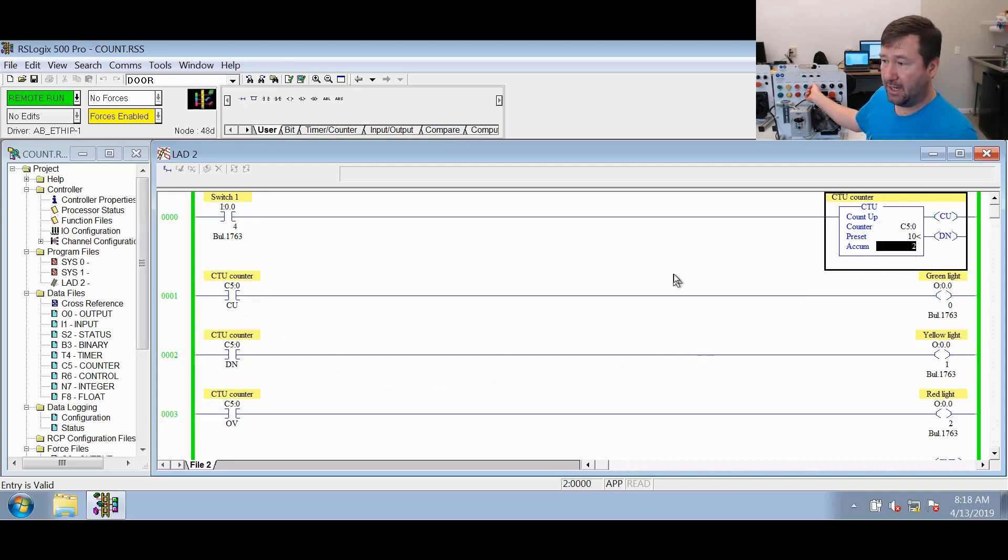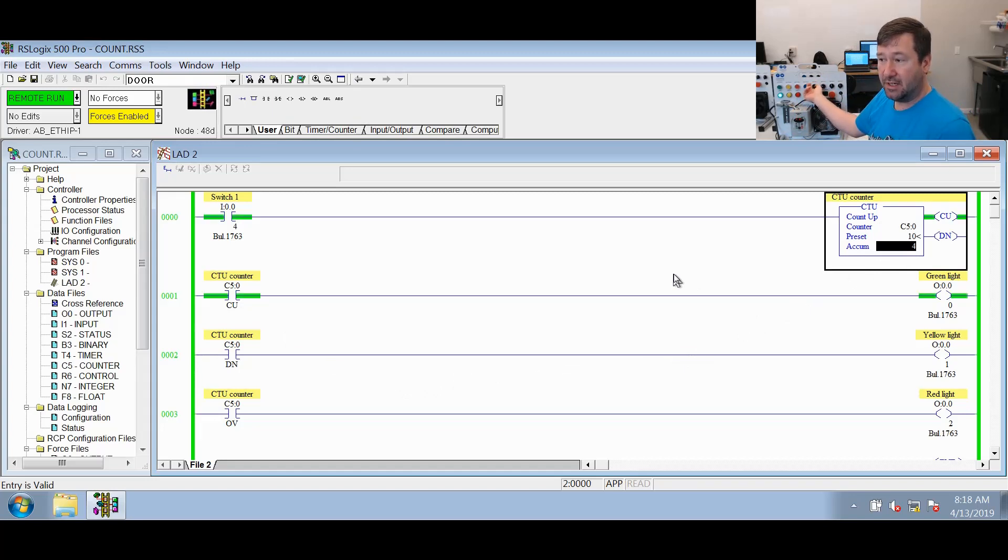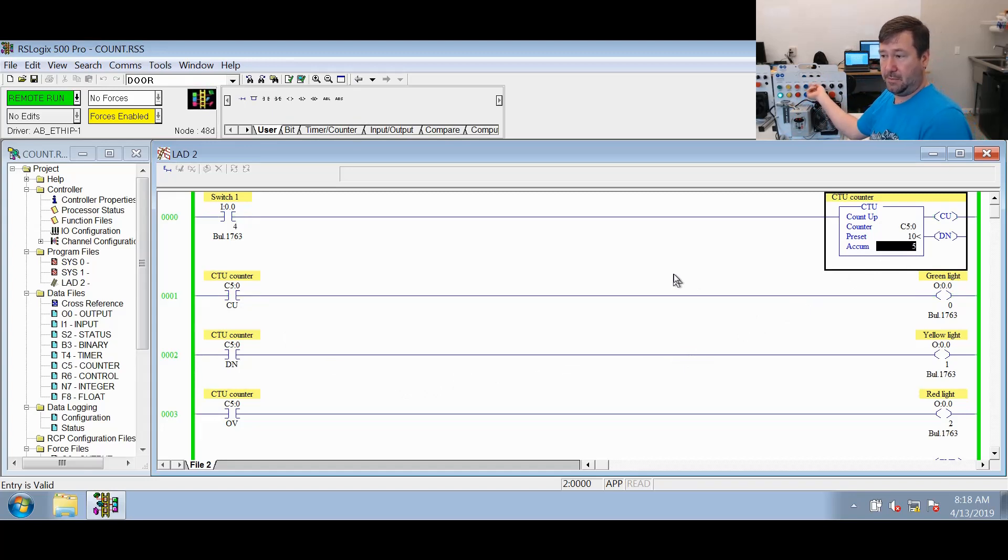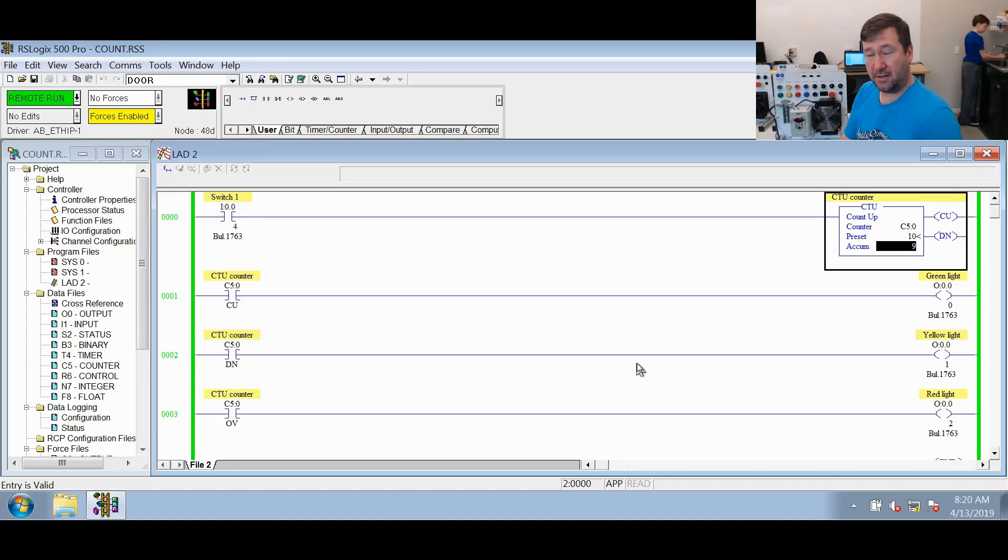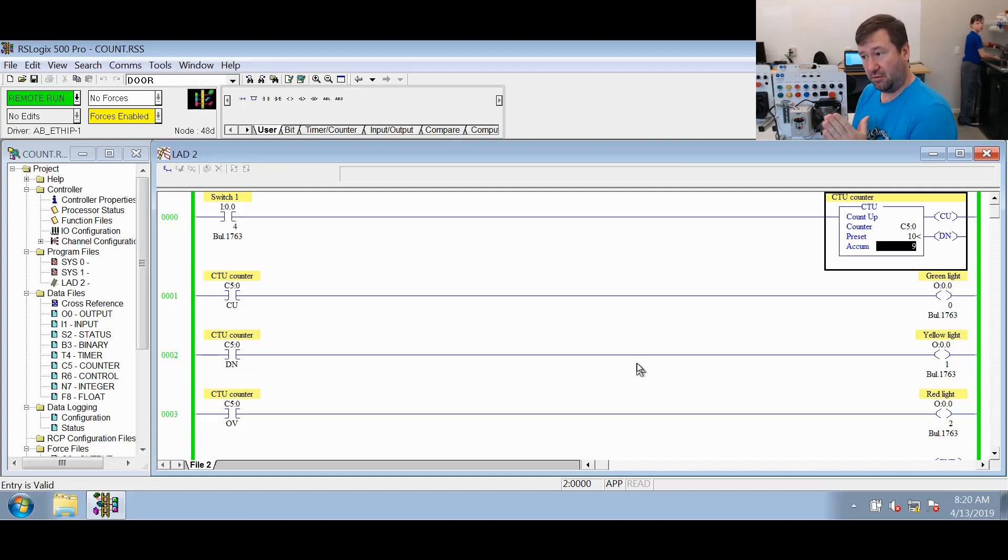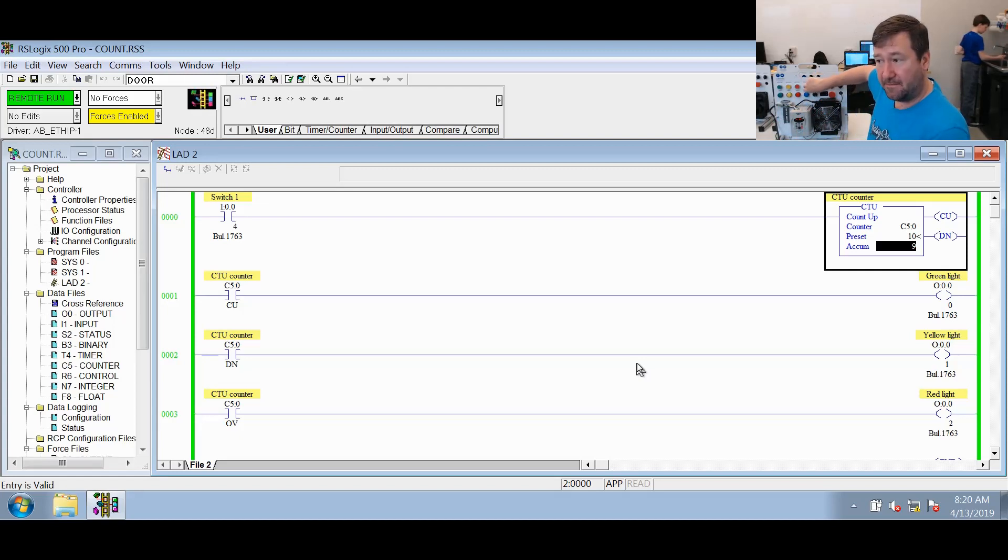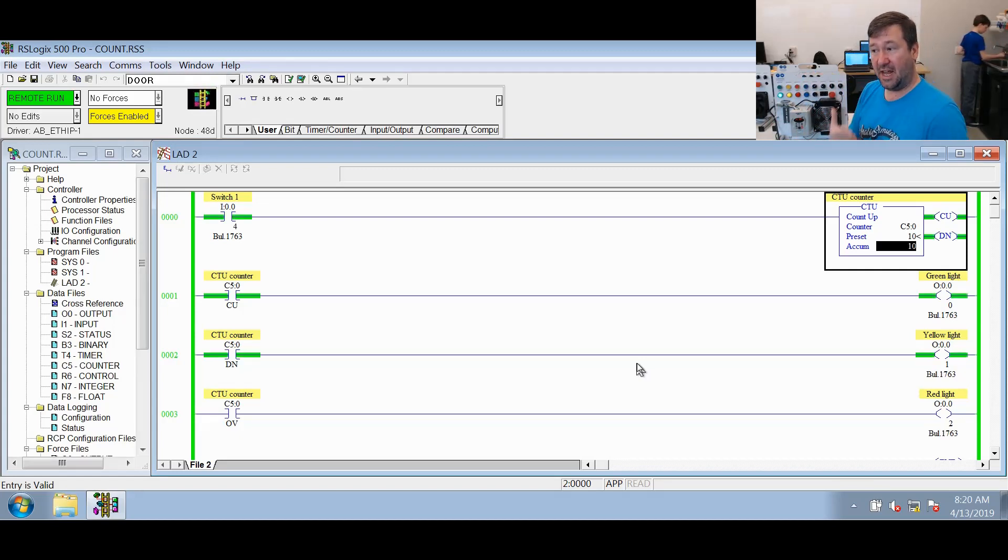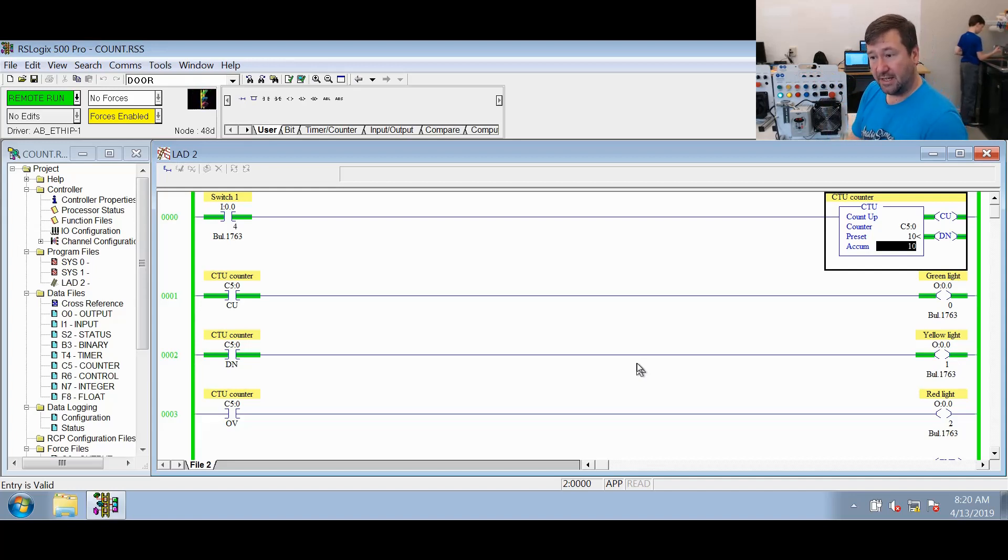So now we'll play with that. Actually, we'll play with another seven times to bring us up to a value of nine. Now our accumulated is nine, our preset is 10, so we're right at this counter being at the preset value. And we're going to switch it that final time. You see now our accumulated value is equal to our preset, so our done bit is now a one.